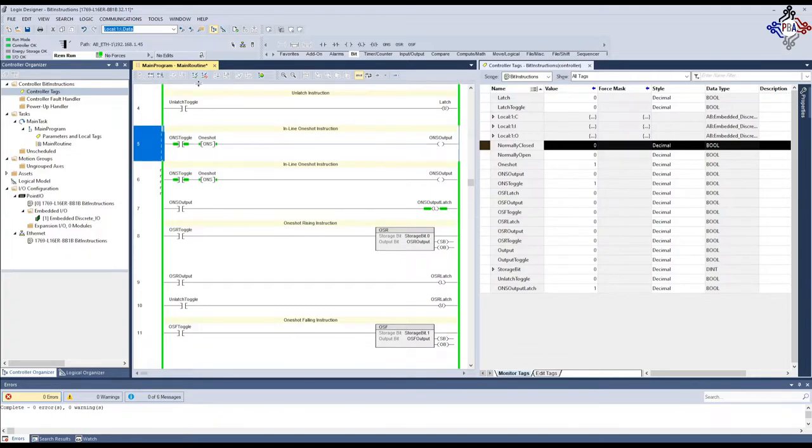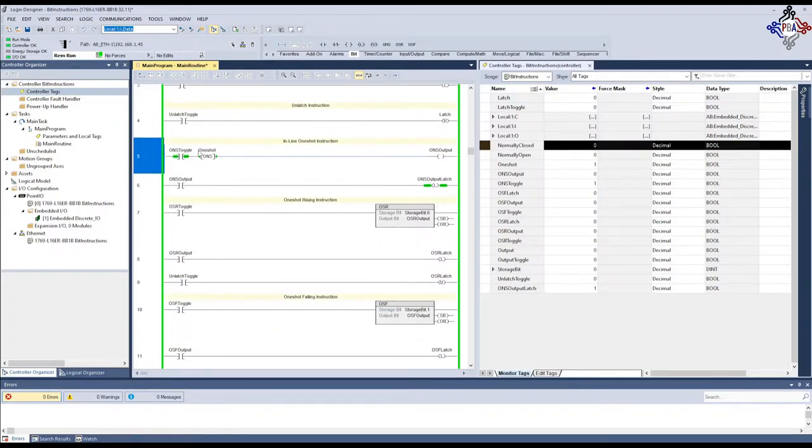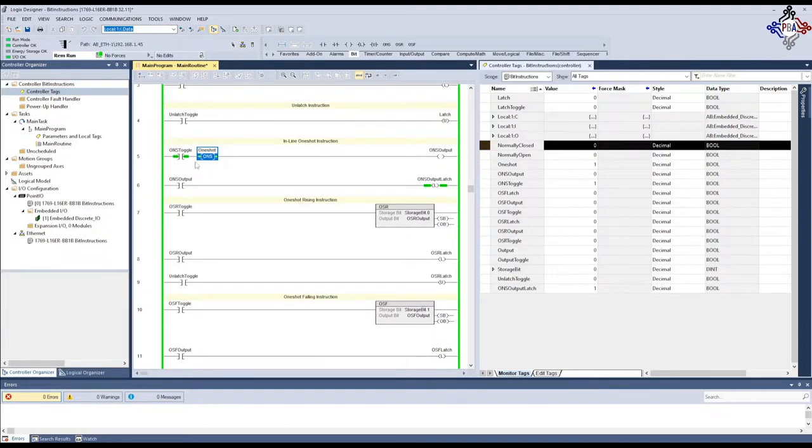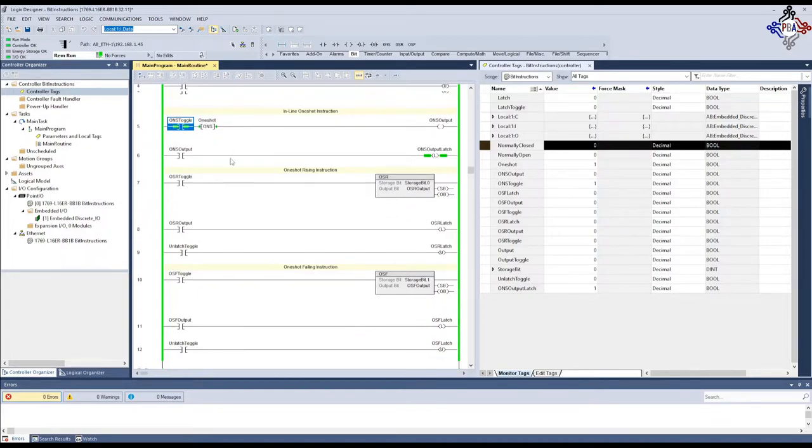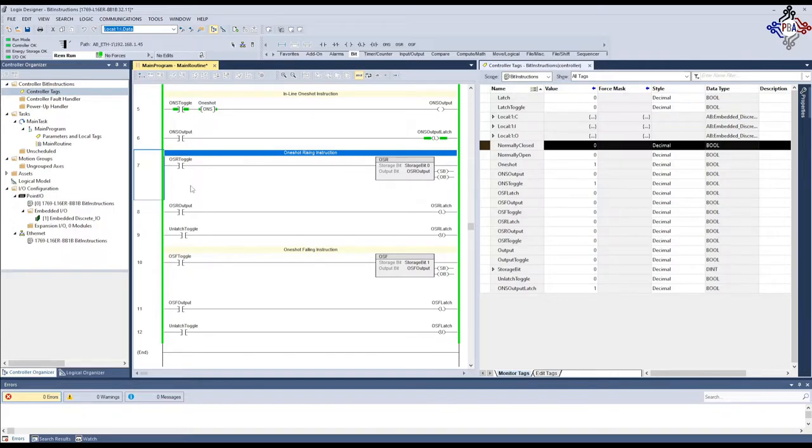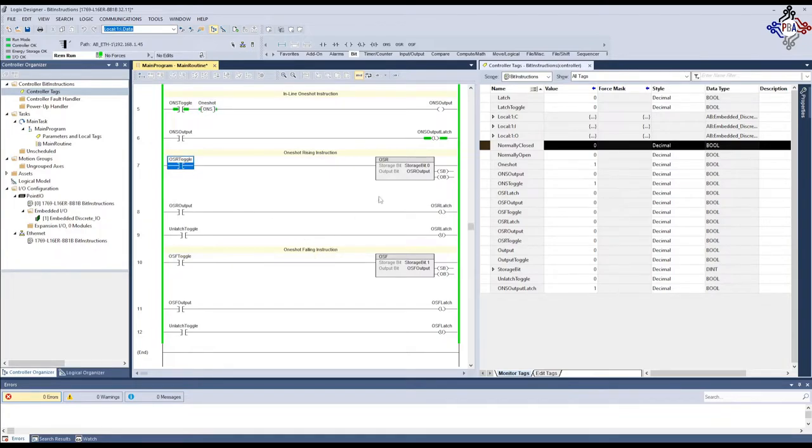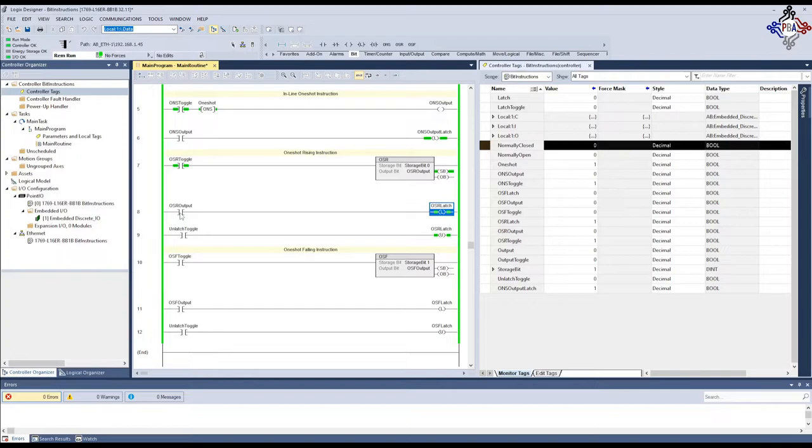The next one-shot is called the OSR. This is something you'll find in older SLC 500 controllers also. Back to RSLogix 5, the PLC5 stuff, and very old things. They used only these OSR and OSF. You didn't have the nice convenient ONS function. So, to do the OSR, you'll see it's very similar to this ONS instruction up here. I turn it on, and instantly it latches this output. But, it doesn't latch the OSR output. I turn it off, I unlatch, and it unlatches. Now, you'll notice the difference between these two. One shot rising, one shot falling.